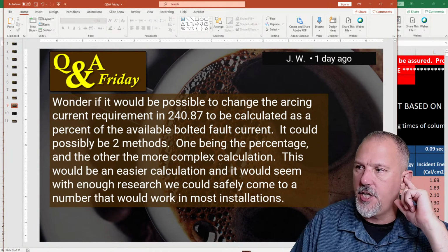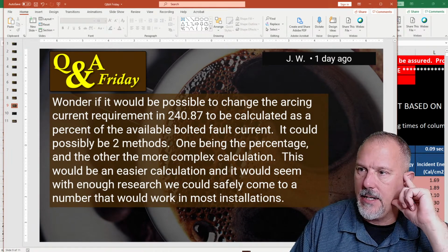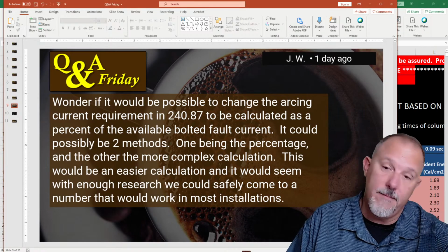Wonder if it would be possible to change the arcing current requirement to calculate it as a % of the available bolted fault current.